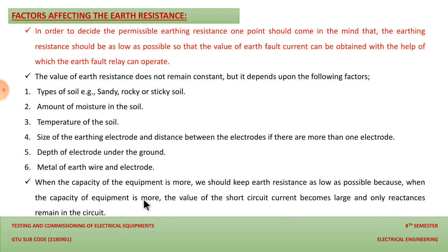And when the capacity of the equipment is more, the value of the short circuit current becomes large. So we should keep the resistance as minimum as possible, so that the heavy charges can transfer through that earth electrode. And only reactance remains in the circuit. So resistance will become zero, or we can say negligible, and the reactance of that earth electrode will remain in the circuit.